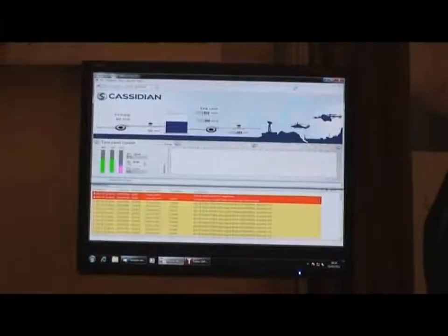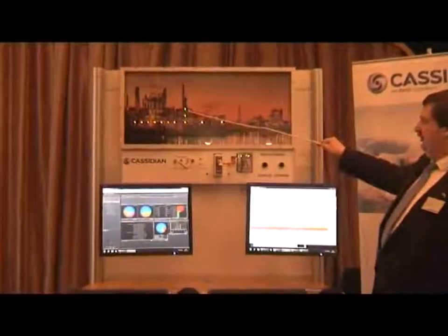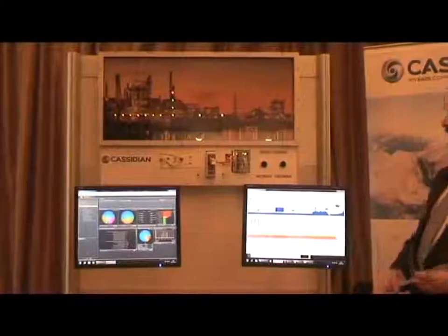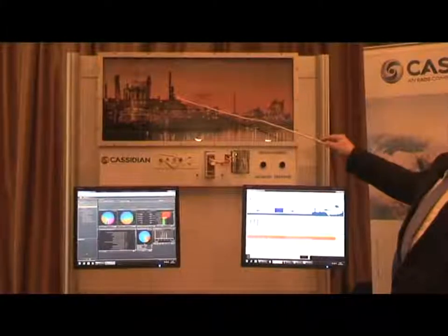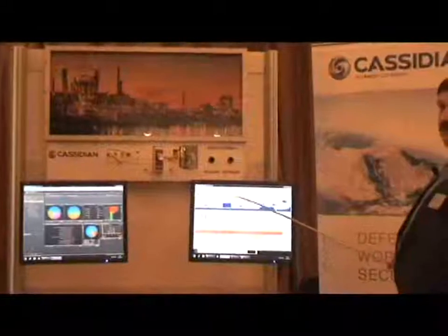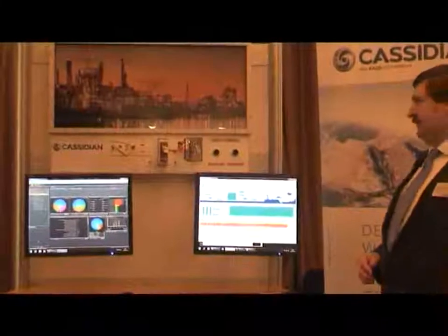So the control operator goes, "Oh, I must have a look at that," and he clicks on it to open it. What he doesn't realise is there is actually a piece of malware in that update which is now going to attack the PLC. So we have running now some malware. If we look back up the top, we can see that there is an overflow happening. The input pipeline is being driven. The system is running up and filling the tank. But in the control room, there is no idea. So we have an alarm sounding now. That tank is actually overflowing refined product out the top because it's full. In the control room though, the operator thinks everything is normal. And the PLC itself has died because it has now been overwritten by the attack.